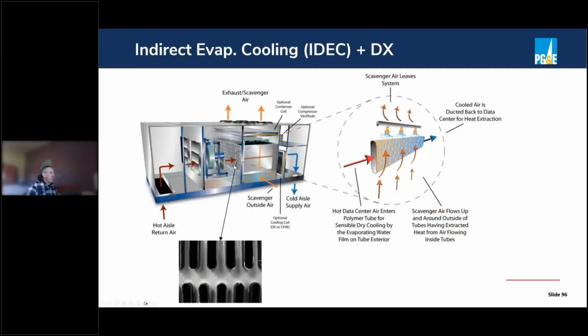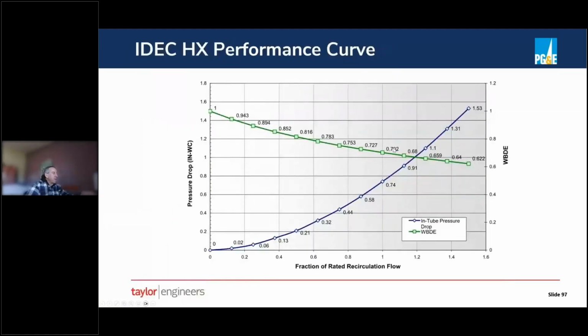Another picture of that same unit, sort of showing a little bit more what that heat exchanger looks like. There are spray nozzles that spray water on the outside of these tubes. And then the recirculated air goes through the tubes on one side, and on the other side, there's heat transfer through the cooled surface with the spray on it. Some interesting features about IDEC performance. This graph is showing the wet bulb depression effect, so how effective that heat exchanger is as a function of the airflow rate.